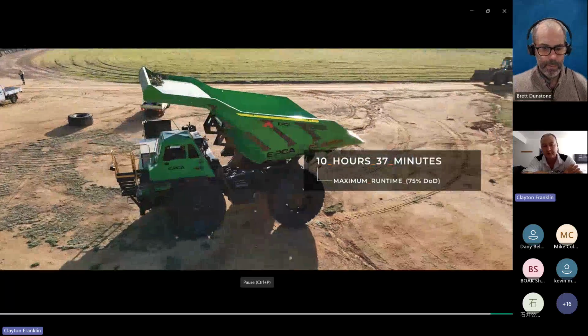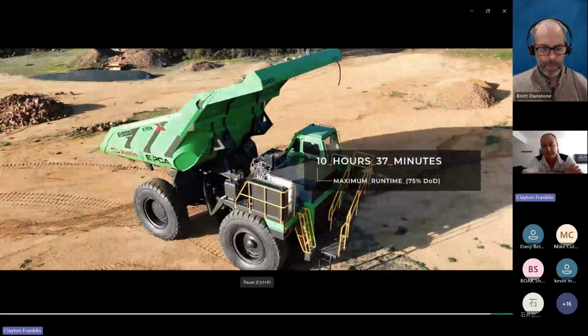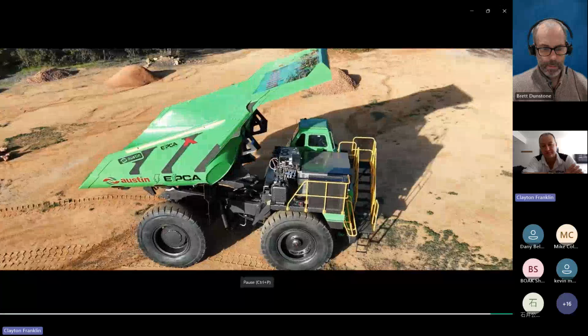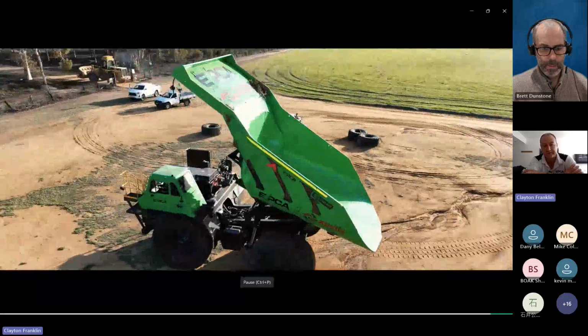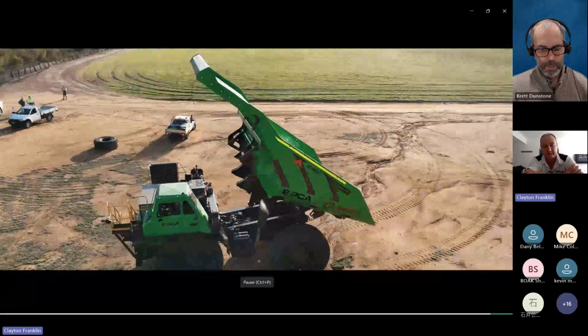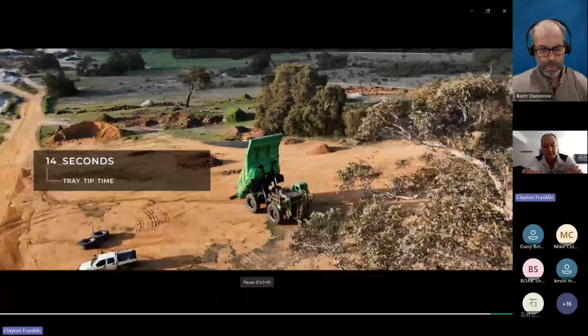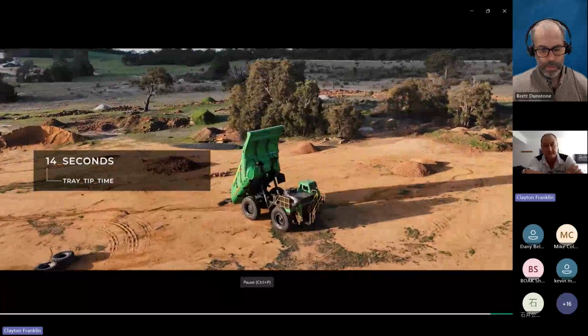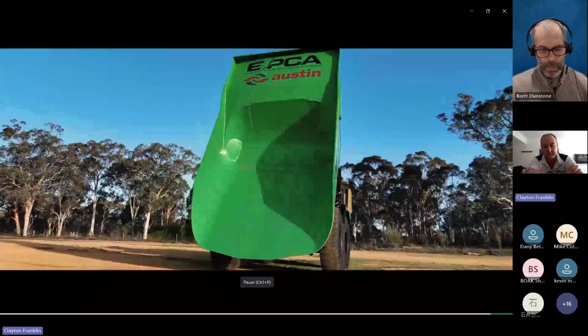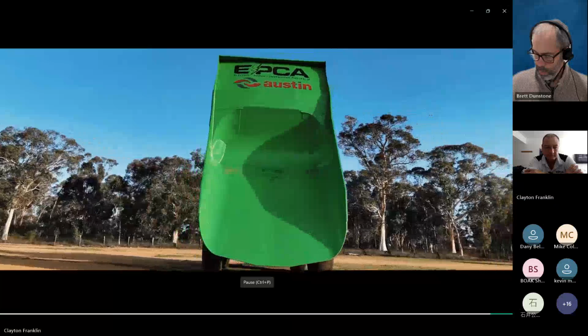We found not 8 hours, but 10 hours 37 minutes for a 75% depth of discharge. You can bring these batteries down to 90%, so we can get even longer run time, which we were blown away by. Same tray tip time, because it's the same mechanical components.